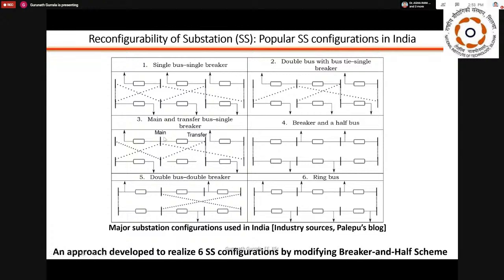And then you have main and transfer bus, which also has 2 buses, but there is a slight difference between double bus and main and transfer. In a transfer bus, it can take only one feeder at a time. It cannot take all the feeders, whereas in a double bus, both the buses have the same capability. And then you have what is called the breaker and half scheme, where for every feeder that you have, there are two breakers which need to be controlled to isolate this energized device. Essentially, there are two buses which are active or energized in this scheme.